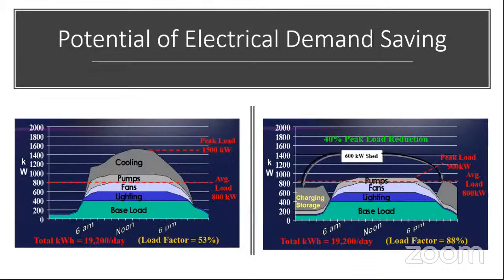Potential of electrical demand saving. Let us have a look at these graphs one by one. Let us see the first one, the one on the left side. This graph typically shows a load profile of the building, and it's a 24-hour load profile. It starts from here and goes until here, and if we try and calculate the average load of this building, the peak load happens to be 1500 kilowatt at some time. However, the average load over 24 hours happens to be nearly 800 kilowatts.